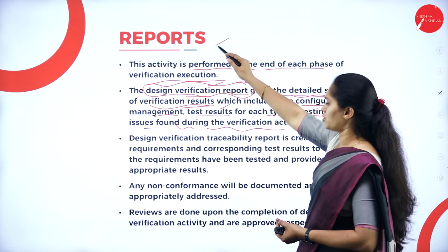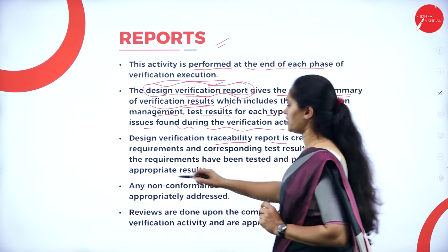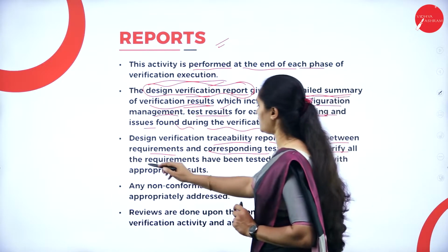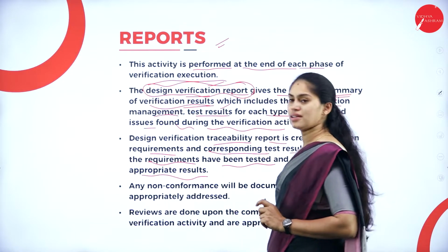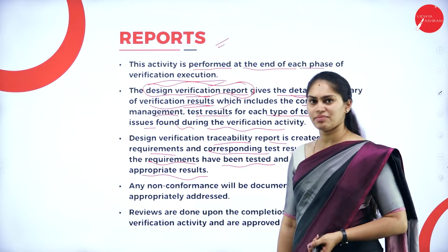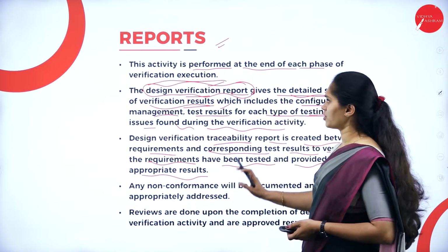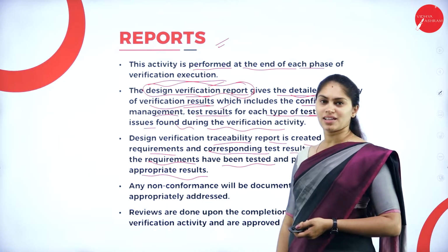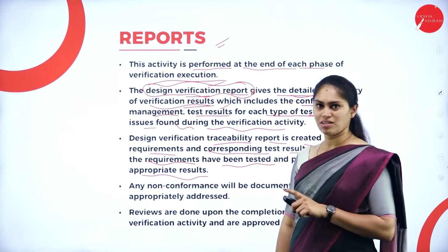Also, for the traceability activities, a report is created between the requirements and the corresponding test results to verify that all the requirements have been tested and provided with appropriate results. So whatever test cases we have, whether pass or fail, all those requirements are saved in the reports. These are the phases we have in the design verification process.